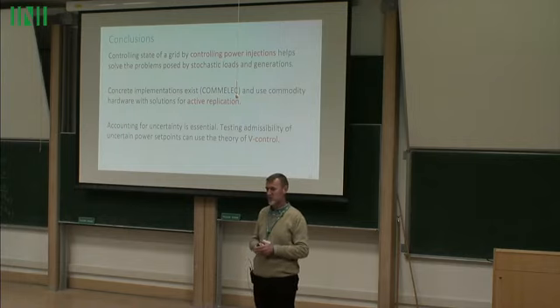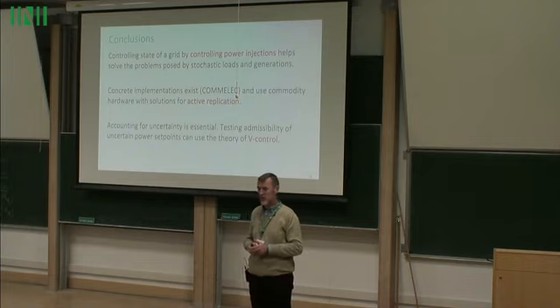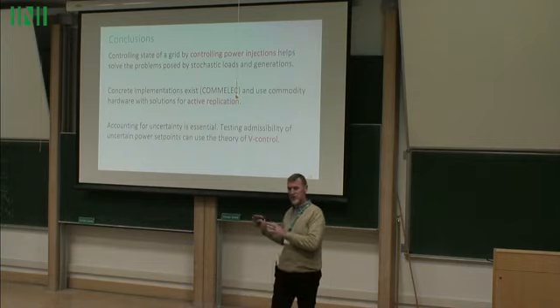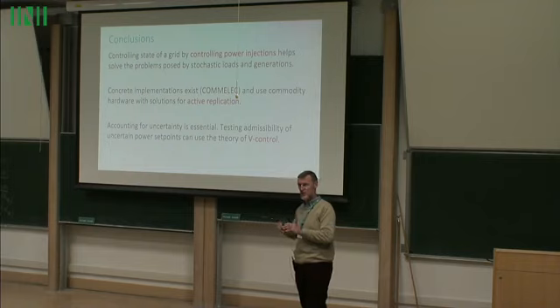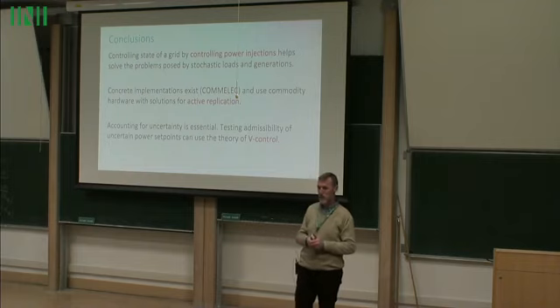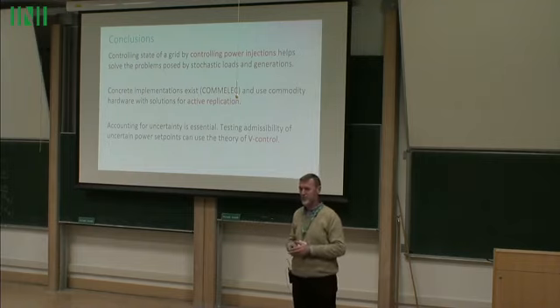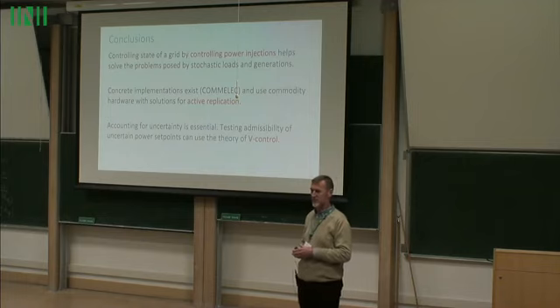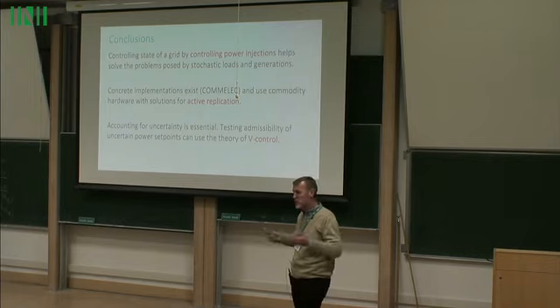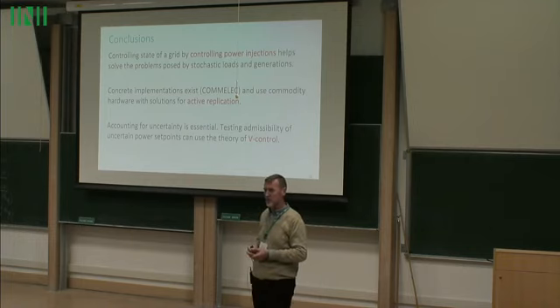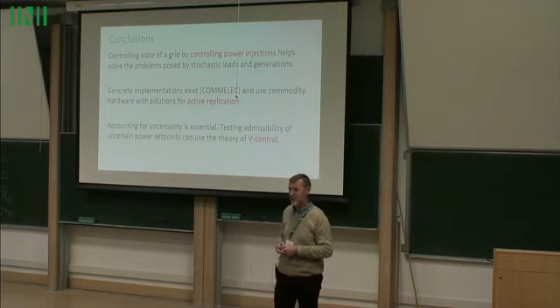Regarding synchronization - do you have synchronization issues, and how much do you depend on GPS? This is all synchronized: we receive GPS and then distribute it with PTP and the White Rabbit system. So you have synchronized topology and measurement - yes, both, sure. For the PMU measurements we have hard synchronization requirements everywhere, but for the status of the breakers, sometimes.